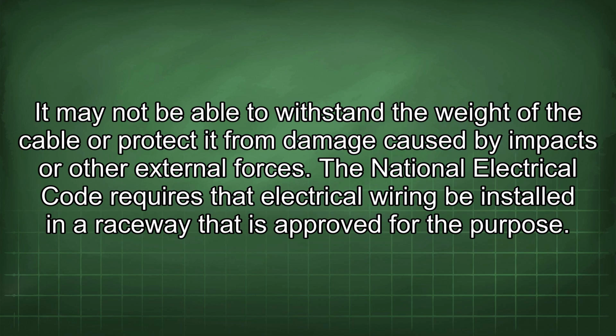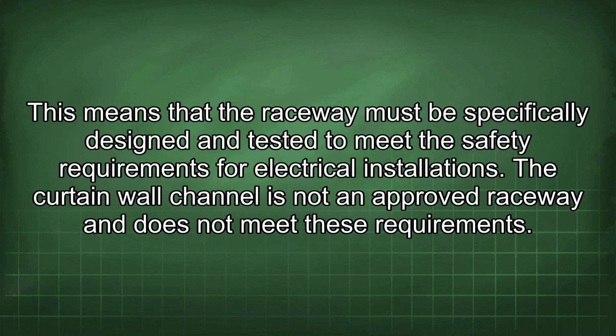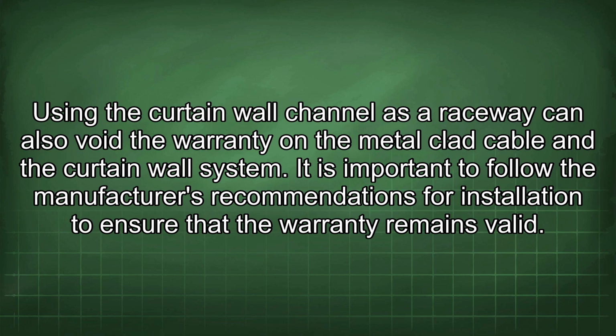The National Electrical Code requires that electrical wiring be installed in a raceway that is approved for the purpose. This means that the raceway must be specifically designed and tested to meet the safety requirements for electrical installations. The curtain wall channel is not an approved raceway and does not meet these requirements. Using the curtain wall channel as a raceway can also void the warranty on the metal-clad cable and the curtain wall system. It is important to follow the manufacturer's recommendations for installation to ensure that the warranty remains valid.